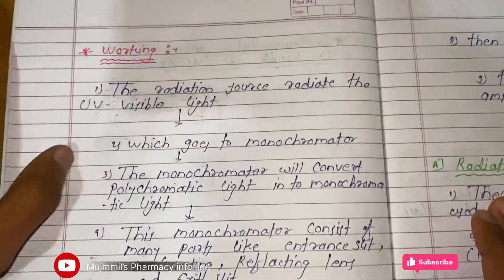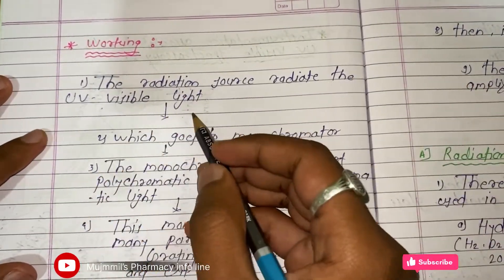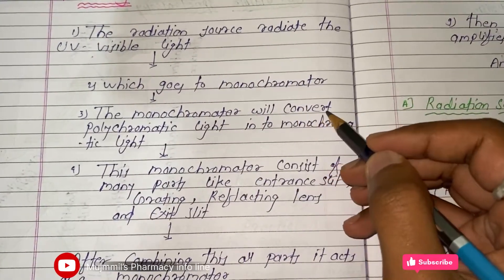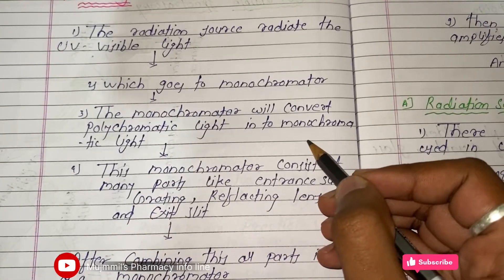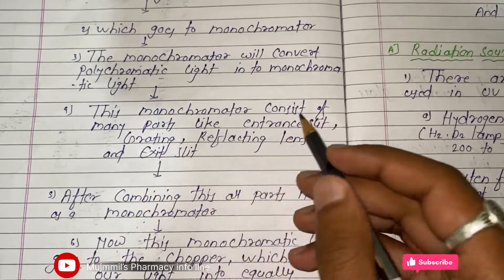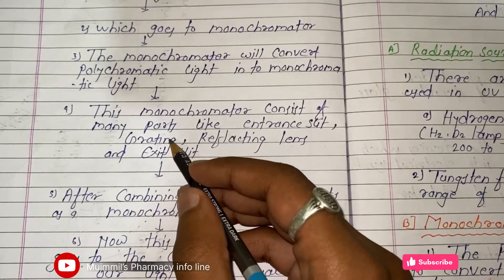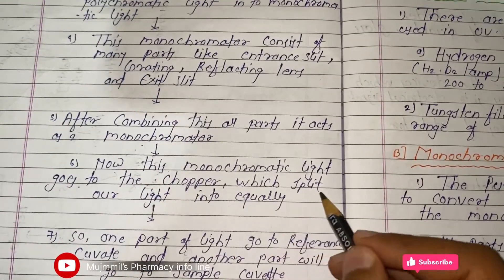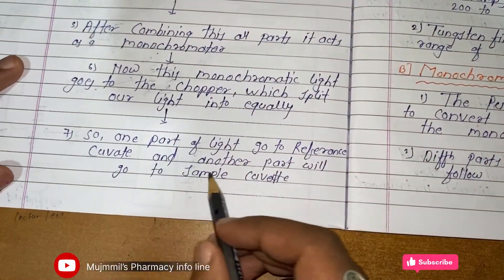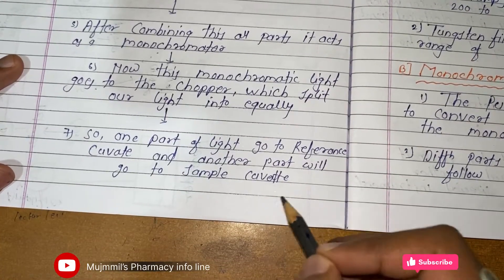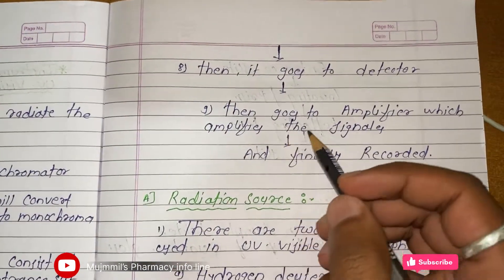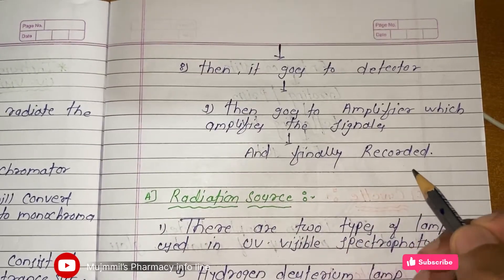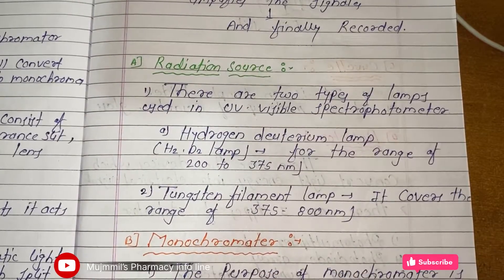In detail: the radiation source radiates UV-Visible light, which goes to the monochromator. The monochromator converts polychromatic light into monochromatic (single wavelength) light. The monochromator consists of an entrance slit, gratings or prism, reflecting lens, and exit slit. The monochromatic light goes to the chopper, which splits it into two equal parts — one to the reference cuvette and one to the sample cuvette. Detectors convert light energy into electrical signals, the amplifier amplifies them, and the result is recorded.